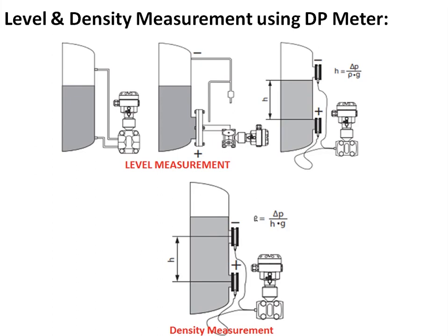For level and density measurement using a DP transmitter: the level measurement is done using a DP transmitter. The pressure exerted by the liquid level is proportional to rho × G × H. The height of the liquid is measured by measuring the differential pressure, given as H = delta P / (rho × G).